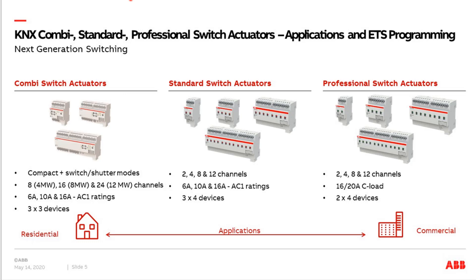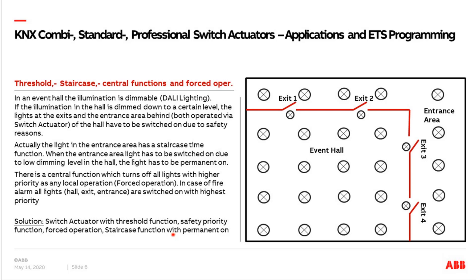Today I have created an ETS project. Let me first explain what is behind this project and which functions are behind, before going directly into the ETS. We have a so-called event hall with some lighting controlled not with switch actuators but with a DALI gateway. The lights in the entrance area and also the exit light next to the doors are controlled via switch actuators. If you dim down the light in the event hall and undershoot a certain level, then both the exit light and the entrance light must be switched on due to safety reasons, so it's not too dark.